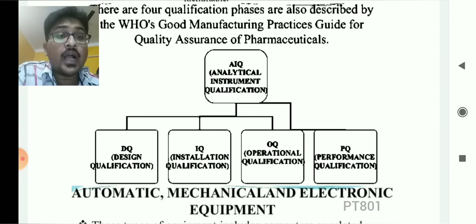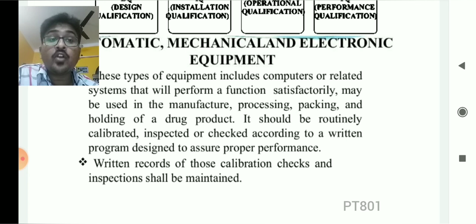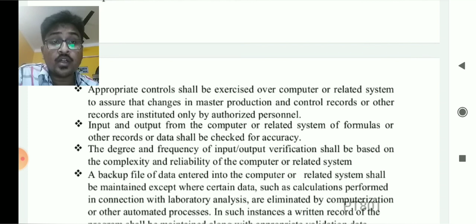Now nowadays the different equipments that are being used are automated because they are operated through computer software. Now if the system is to be maintained, then besides the equipment being maintained, the software is also to be maintained, because if the software crashes, then the operating system won't work, as well as the equipment will also not work. That is why written records of calibration, check, inspection have to be maintained, and backup files also have to be entered in the computer for the related system, so that if the system crashes, we can reinstall the system. Input and output of the computer related system formulas and others should be checked for accuracy.